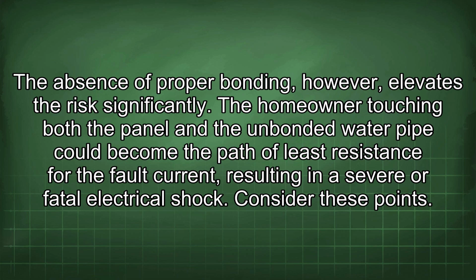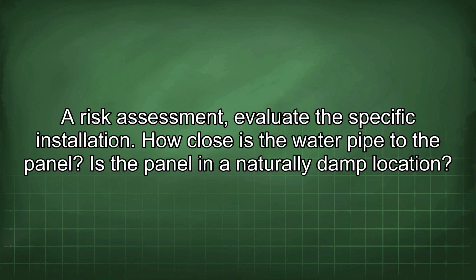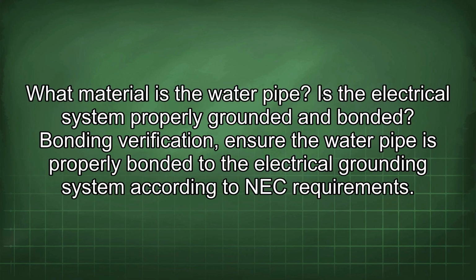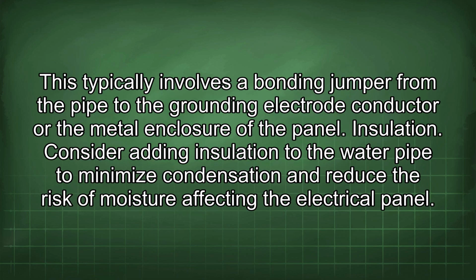Consider these points. A risk assessment: evaluate the specific installation. How close is the water pipe to the panel? Is the panel in a naturally damp location? What material is the water pipe? Is the electrical system properly grounded and bonded? Bonding verification: ensure the water pipe is properly bonded to the electrical grounding system according to NEC requirements. This typically involves a bonding jumper from the pipe to the grounding electrode conductor or the metal enclosure of the panel.